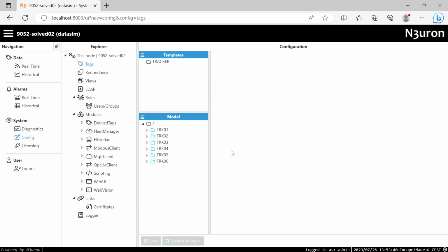The first thing you do when working with a template is declare a template definition. A definition is effectively the master copy of the template, and it should fully or mostly define how we want our custom structure to look. Once we set up a definition that outlines our structure, we create any number of instances which inherit the structure from the corresponding definition they're derived from. So, if we have a template definition with a specific number of tags, each template instance will have the same number of tags. So just to reiterate, a definition declares a template structure effectively like a design specification, and then an instance is an actual collection of tags following that specification.